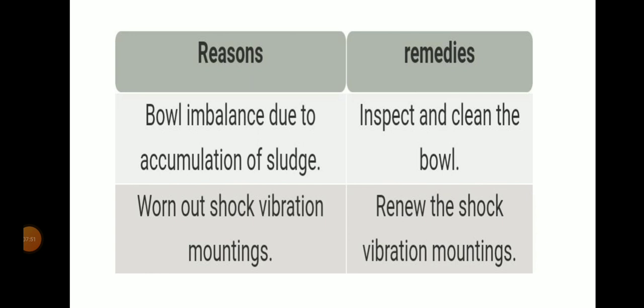Reason means bowl imbalance due to accumulation of sludge. Remedies means inspect and clean the bowl. The other reason means worn out shock vibration mountings. So we need to renew the shock vibration mountings.